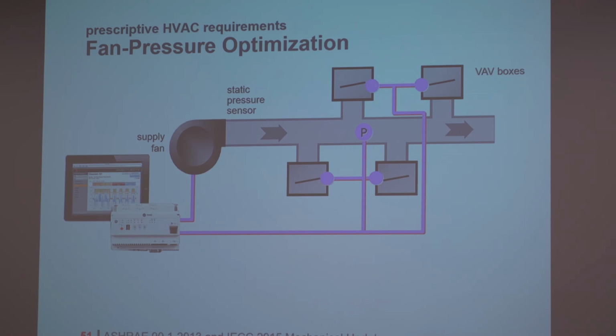Okay, so fan pressure optimization has been in the standard since like 2007. It's been in there for forever. The only change now is that there's some people who are really concerned that rogue, quote unquote, rogue zones would affect the control, because what we were asking people to do is use the critical zone to drive the fan speed directly. So you would poll all the zones and you'd find out which is the most open zone, and if it were all the way open, you would increase the fan speed. If the worst one was partially closed, then we would decrease the fan speed. There was concern that there was always going to be one zone that was never happy. It was at the president's office who had it turned down to 50, or some conference room that was hosting a meeting and somebody modified the set points and never put them back, or something like that.